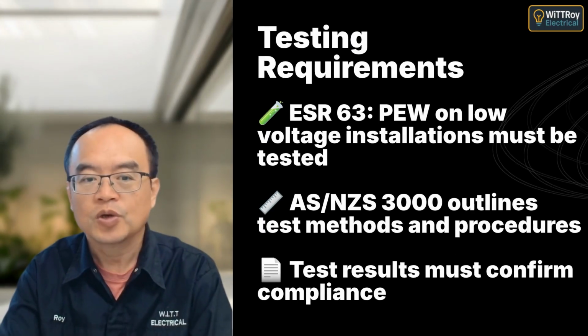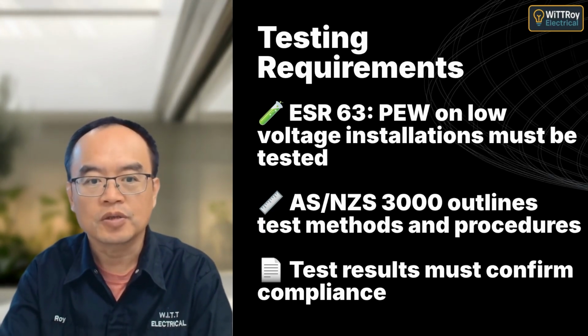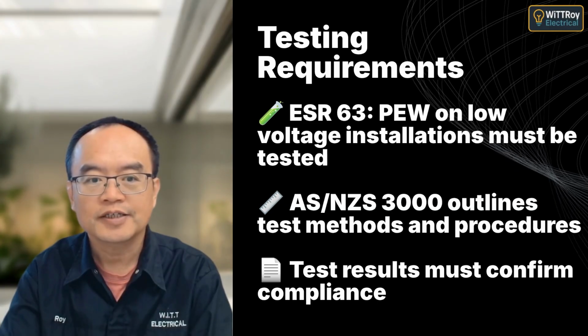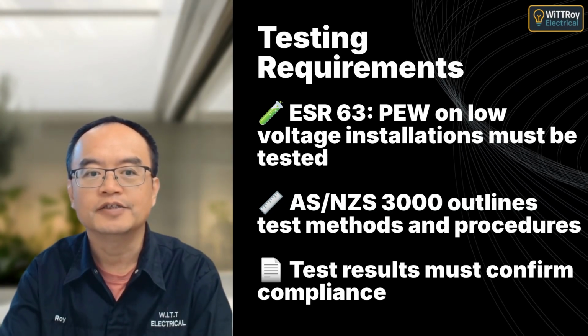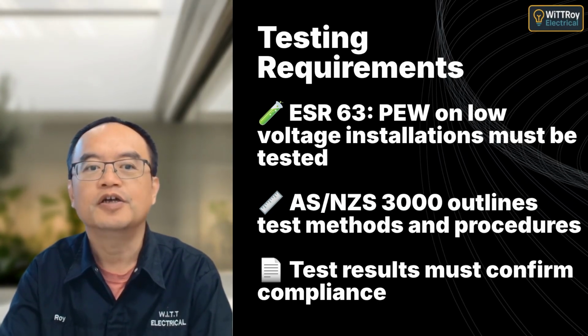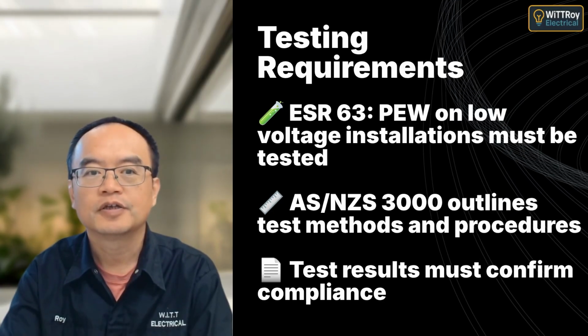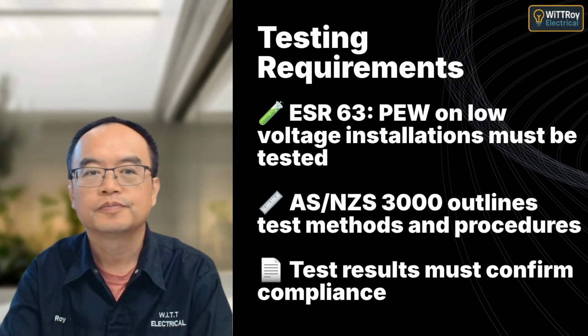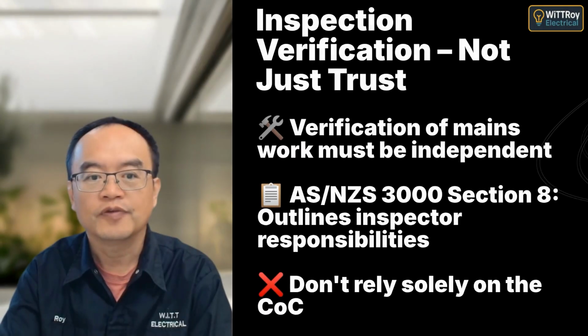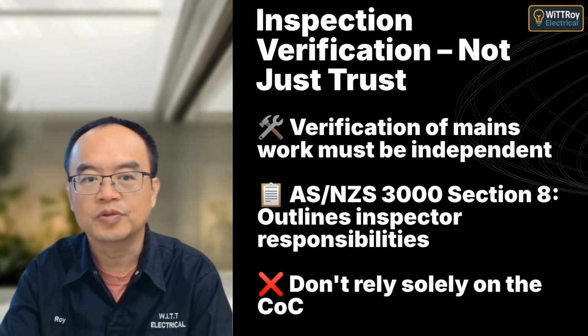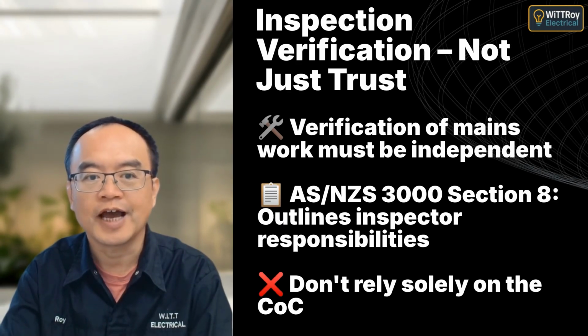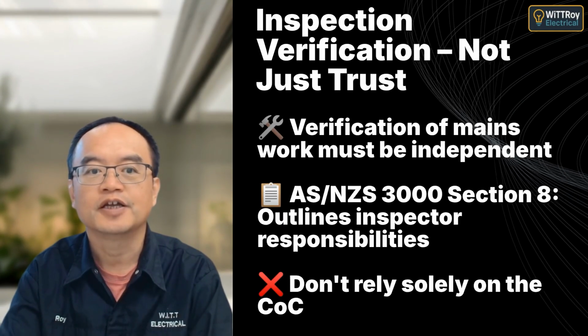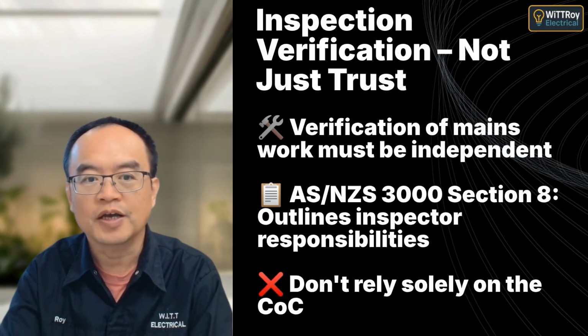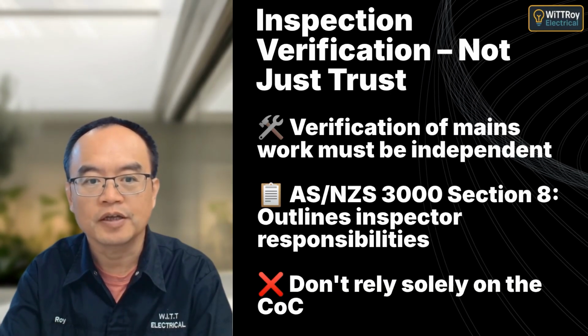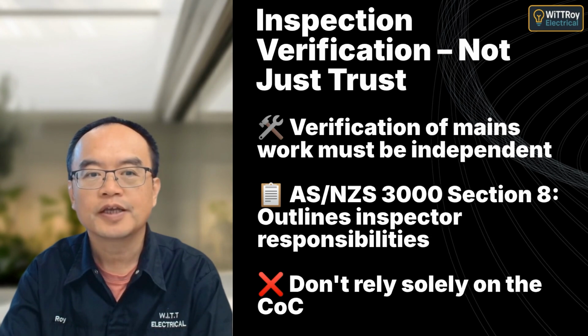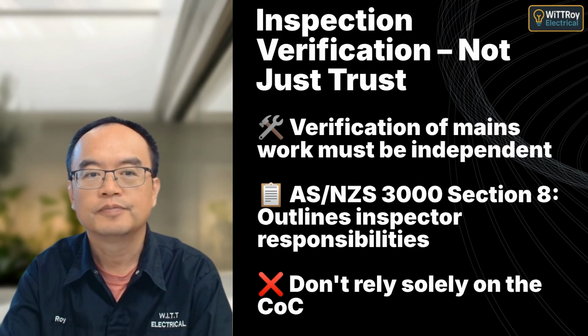ESR 63 requires testing of all PEW done on low voltage installations. That testing must follow the methods in AS/NZS 3000 such as insulation resistance, polarity, and earth continuity. Even if a COC has been issued, the inspector must carry out their own checks. AS/NZS 3000 Section 8 explains what verification tests are required, including inspection of the main earthing system, switchboard wiring, and MEN link.